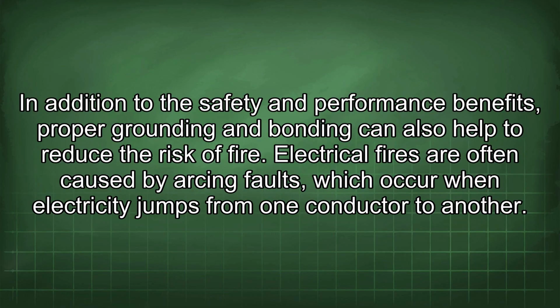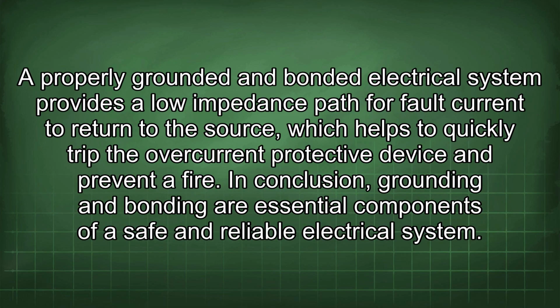In addition to the safety and performance benefits, proper grounding and bonding can also help to reduce the risk of fire. Electrical fires are often caused by arcing faults, which occur when electricity jumps from one conductor to another. A properly grounded and bonded electrical system provides a low impedance path for fault current to return to the source, which helps to quickly trip the overcurrent protective device and prevent a fire.